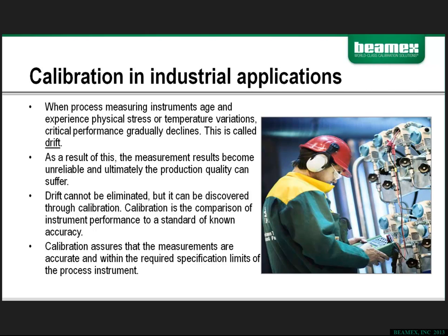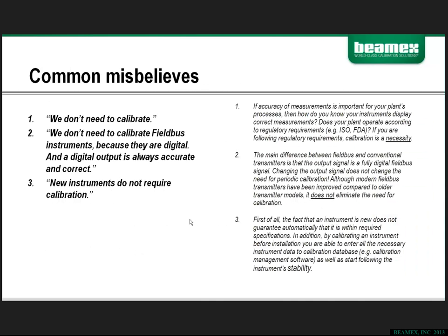Reliability is reduced over time, and without correction can affect production. So drift has the ability to impact every aspect of process manufacturing. Calibration of these instruments based on proper intervals will minimize this drift and reduce its impact on the production process. Some common misbeliefs, and some of these you may not believe that somebody actually said this, but the reality is that we hear these three topics pretty often, and they all have relevance in what you do because they relate directly back to the end result of your product.